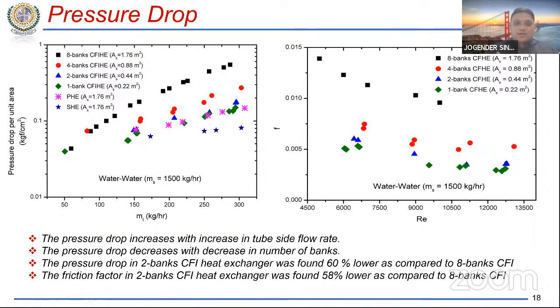Now, since it is increasing the heat transfer coefficient drastically, we wanted to check whether we are losing very much in terms of pressure drop, and we tried to plot the pressure drop here, and also we calculated the friction factor here. If you see this picture on the left hand side, you can see the 2-bank CFI heat exchanger, which is 0.44 meters square. It has approximately the same pressure drop as the 1.76 meters square of PHE and SHE. However, we have already seen that it is providing a much higher heat transfer coefficient as compared to SHE and PHE. And the simple reason behind that is basically the chaotic advection, which we are achieving due to the enhanced mixing process inside the tube.